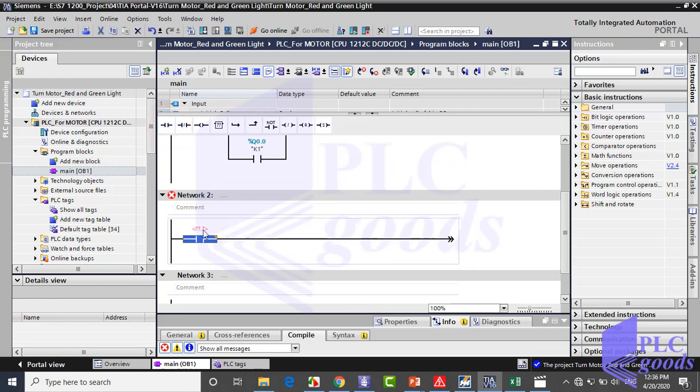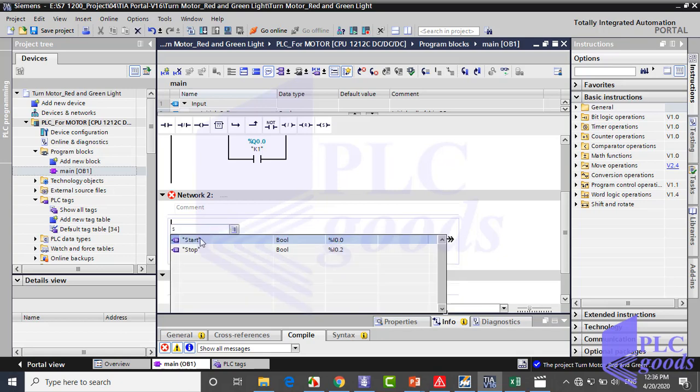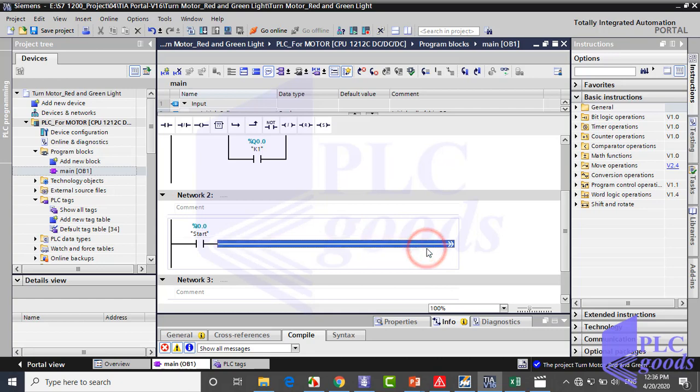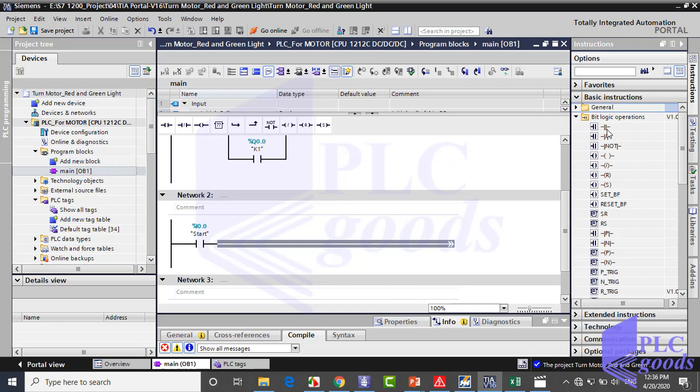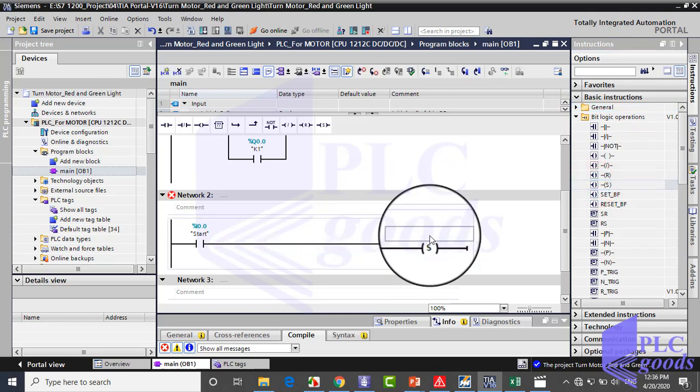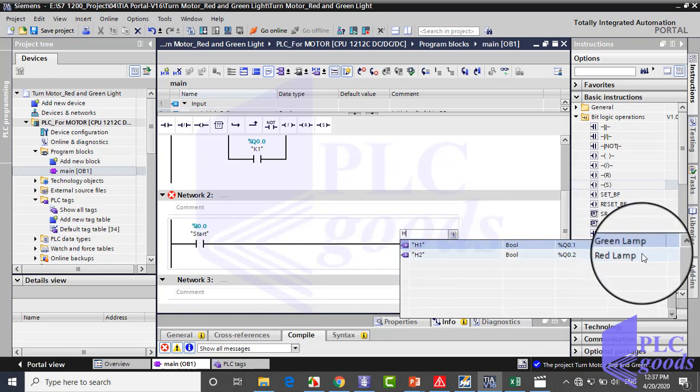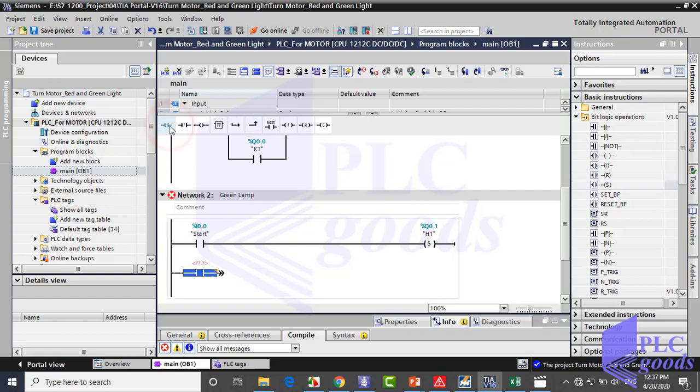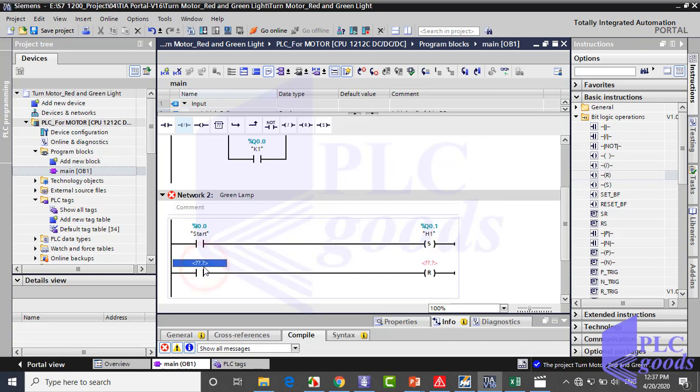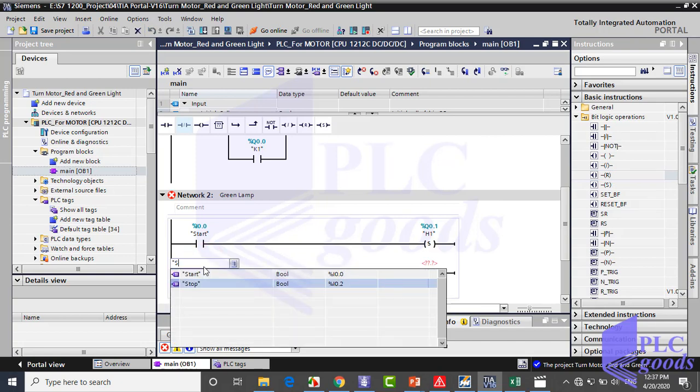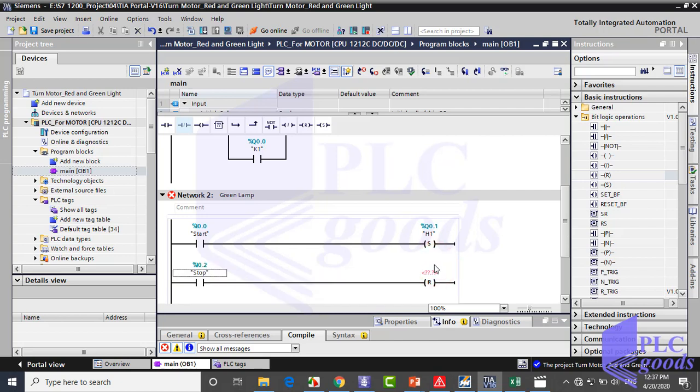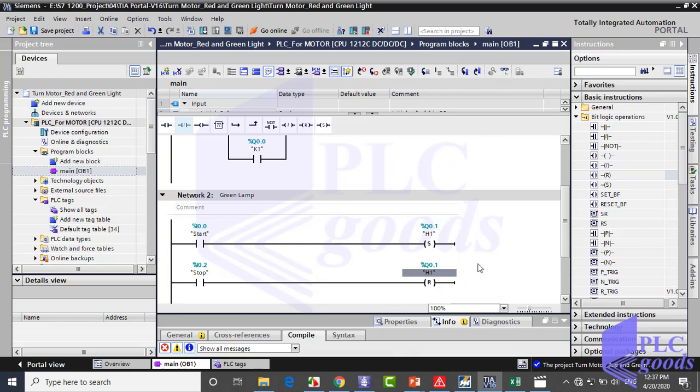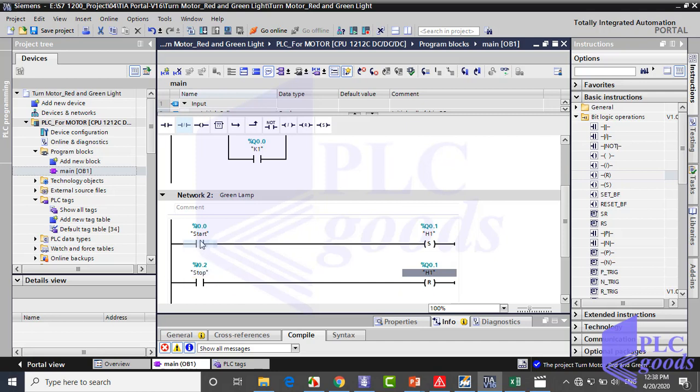That's simple. We need to set the green lamp with start contact and reset with stop contact. So see how I write this program. As you see, I can use tags instead of addresses because we've defined them before in the PLC tags table. This program works like the three-phase motor. Start contact sets green lamp on and stop contact resets it. Pay attention, if both contacts are activated, the green lamp will be off because CPU executes reset instruction after set, so reset has priority over set instruction.